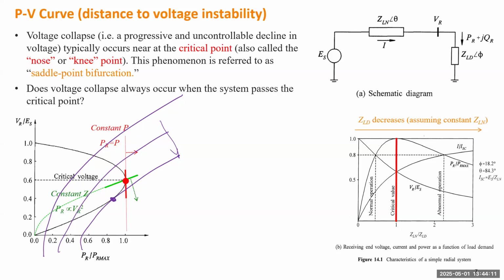And when they use the power flow model to solve the voltage at different loading conditions, in the power flow model, every load bus is treated as constant power, constant P and Q, right? So when you increase the P and Q, you actually assume each load to be a constant power load. So your power flow cannot be solved. What happens is the system will reach a critical point at some areas, at some buses.